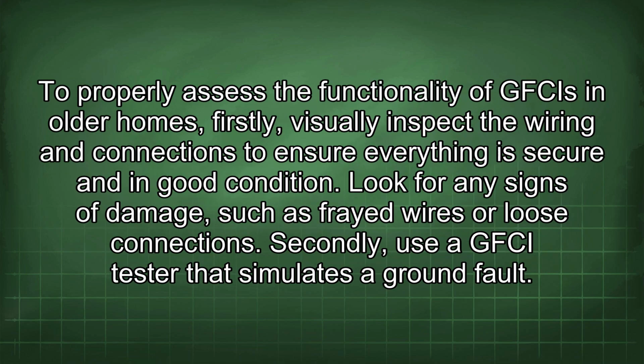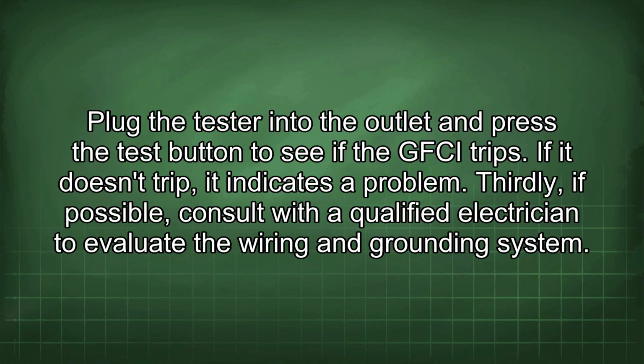To properly assess the functionality of GFCIs in older homes, firstly, visually inspect the wiring and connections to ensure everything is secure and in good condition. Look for any signs of damage, such as frayed wires or loose connections. Secondly, use a GFCI tester that simulates a ground fault. Plug the tester into the outlet and press the test button to see if the GFCI trips.